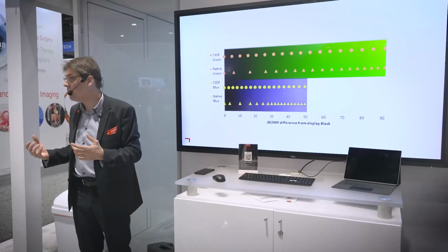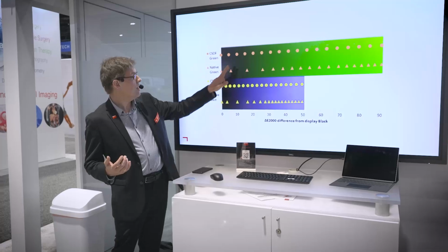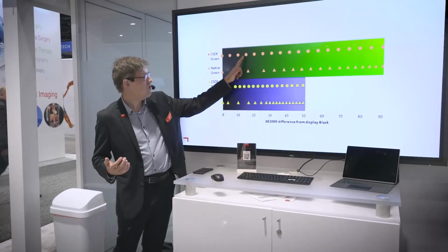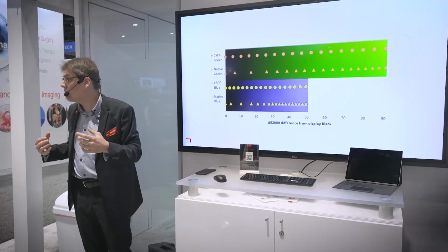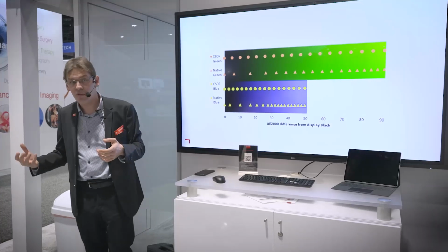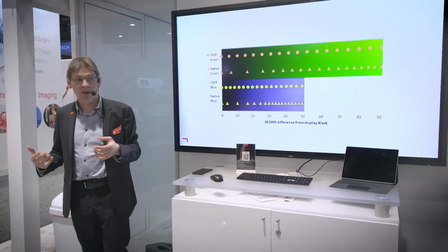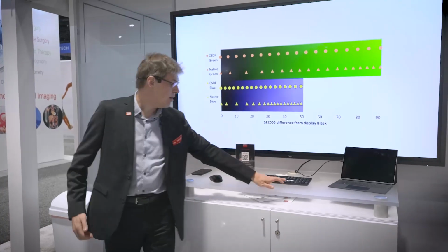So it's not perceptually linear. So if you do CSDF calibration, you're going to redistribute those points on the green axis such that they are all equidistantly placed. And you do that also for the other primary colors, and you do that also for the secondary colors. So in a very simple way, that's how you can do CSDF calibration.